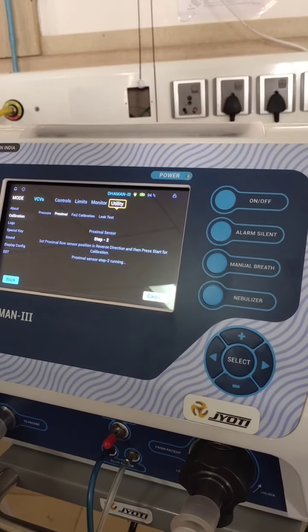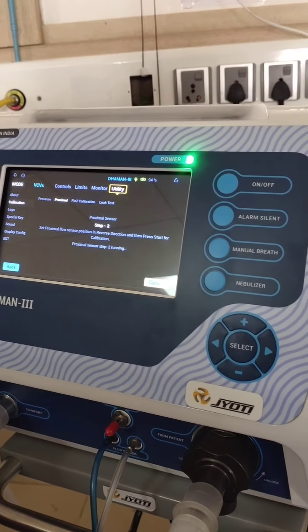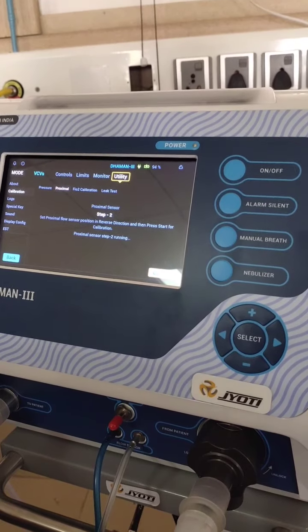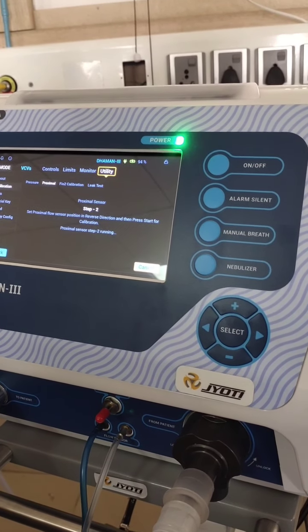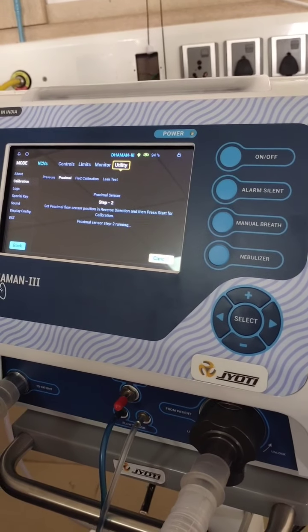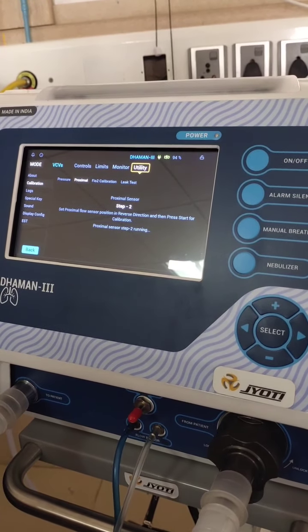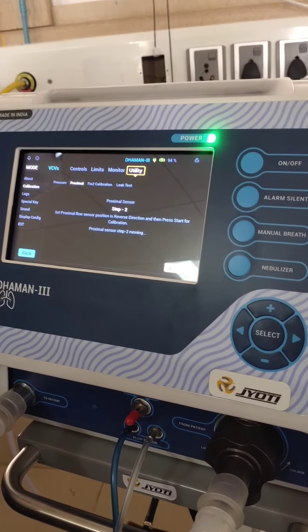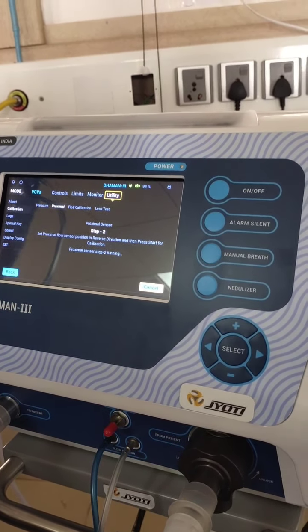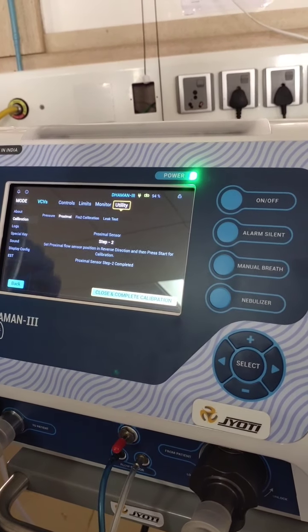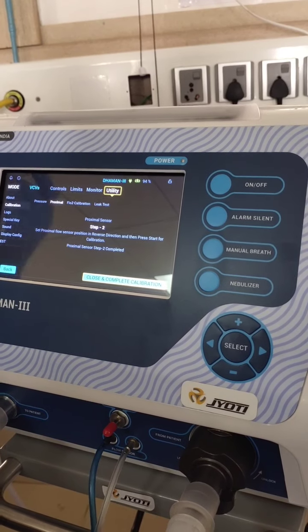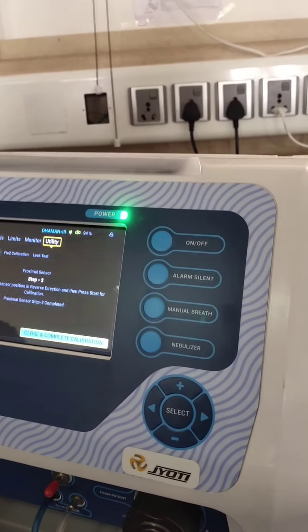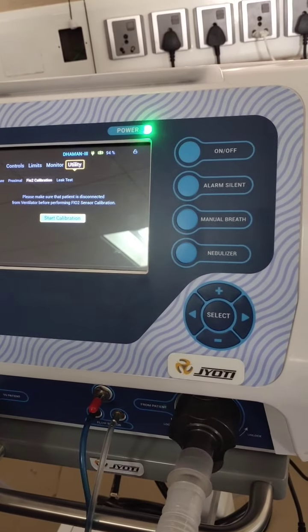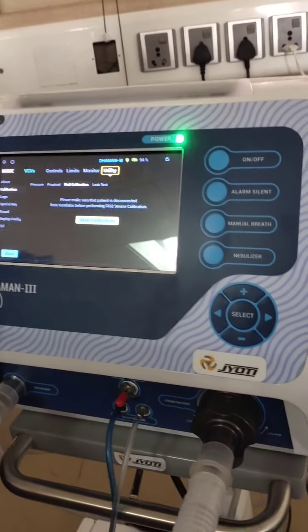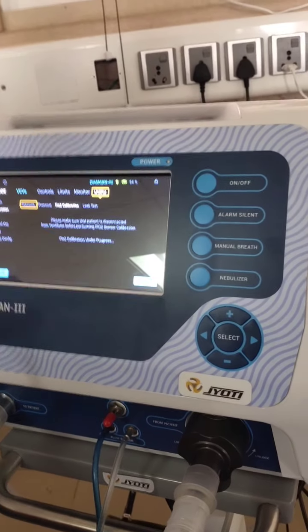Then stop. We have two proximal sensors. These proximal sensors sense the air and O2. If the two proximal sensors are working properly or not, it is cross verifying the flow path. Once it is completed like this, close and complete the calibration. Next is FiO2 calibration. How much is the concentration of oxygen now? We have to calculate. Start the calibration. It will take 3 to 4 minutes.